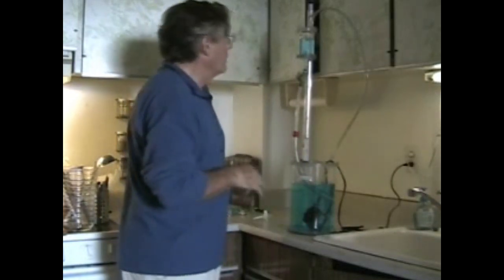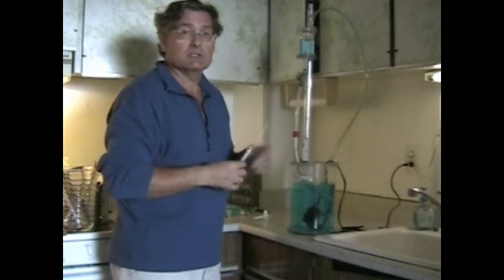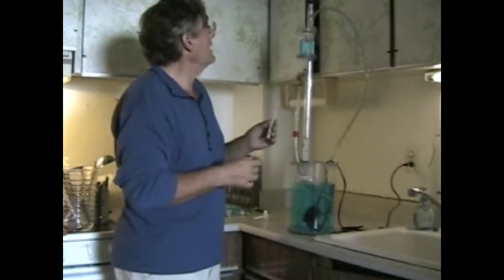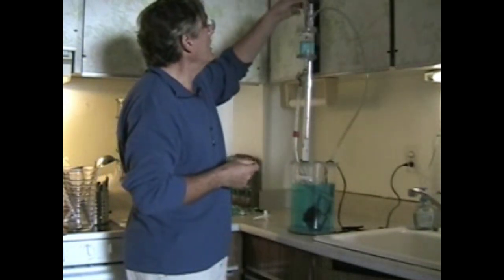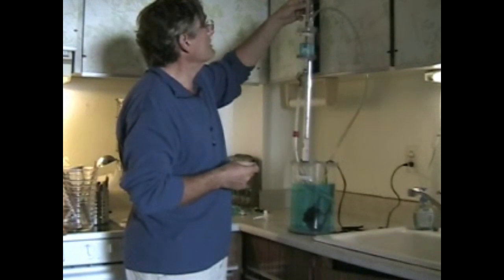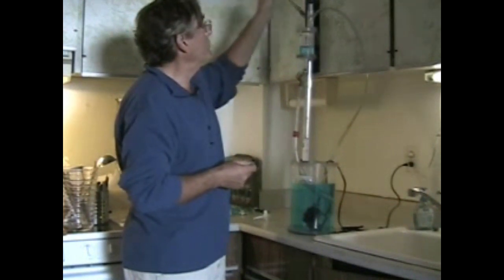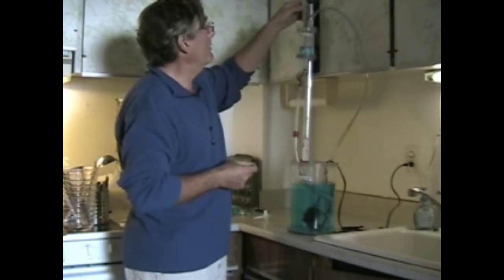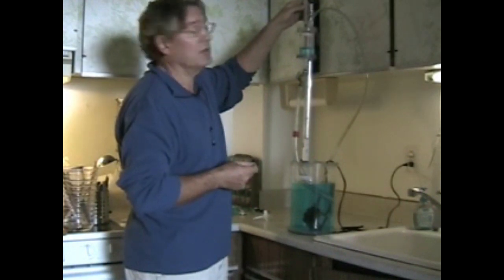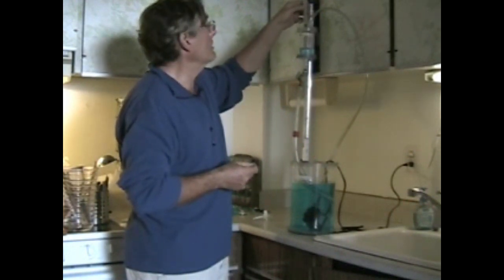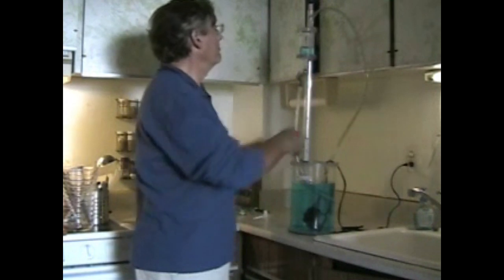One fix for vortexes is to put in baffles in the suction tank. So this can act as a baffle. If I put this in the tank, I can make the vortex disappear here. So you can try combinations of vertical and horizontal baffles, and they will very often solve the vortex problem if you cannot do anything else to change the valve.